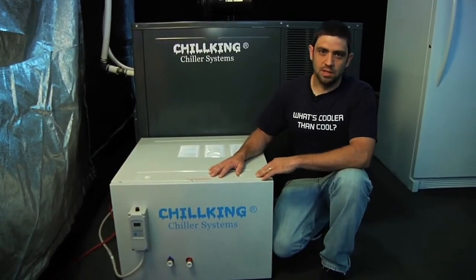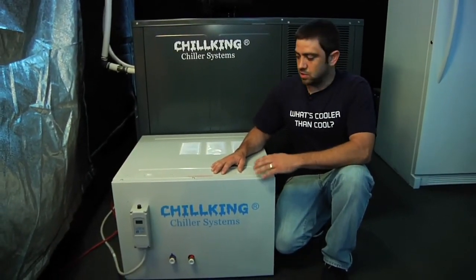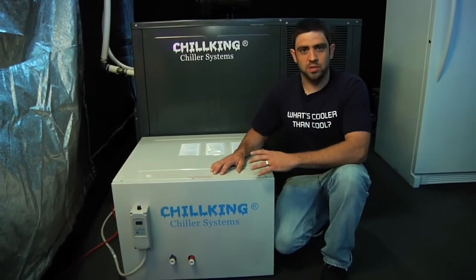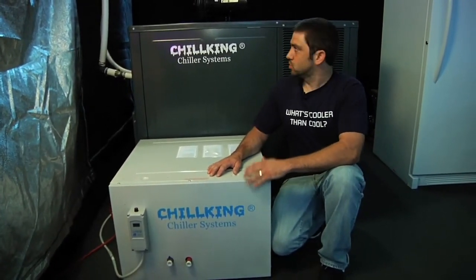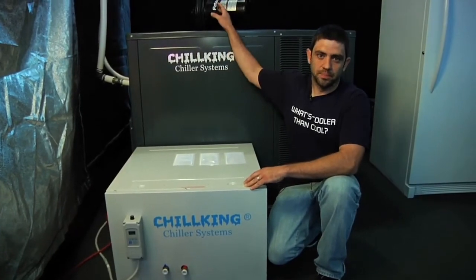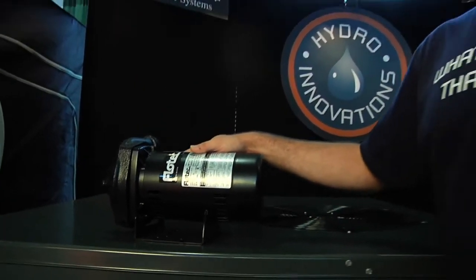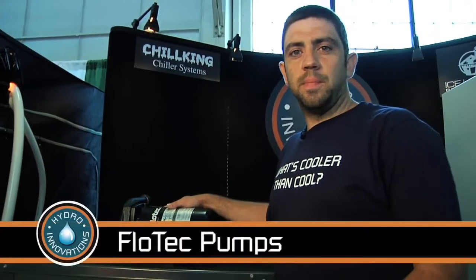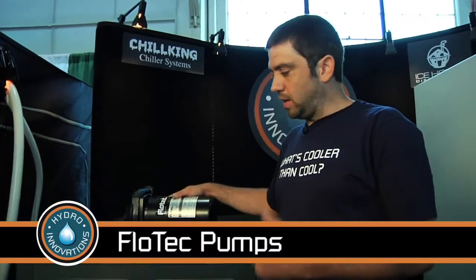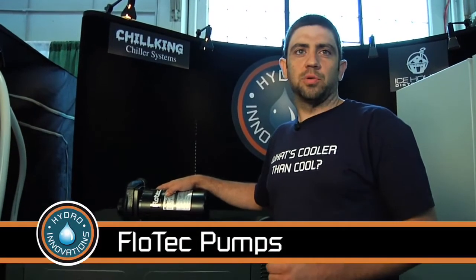We recommend that you use a large pump with these. These units and these systems do not run off of submersible pumps. You need an inline pump, a strong pump like the ones up here. We carry our own line of pumps. These are FloTec pumps made in the USA. They're cast iron, they're made to be used inline, and they are commercial grade pumps. These pumps will last for years and years.